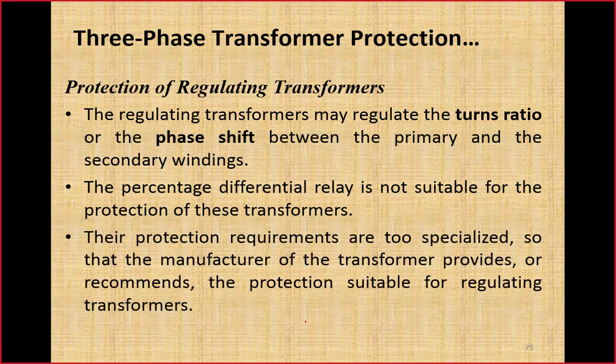Their protection requirements are so specialized that the manufacturer of the transformer provides or recommends the protection suitable for the regulating transformer. For internal faults, we use a Buchholz relay, and for external faults of such a transformer, overcurrent and instantaneous overcurrent relays are used.